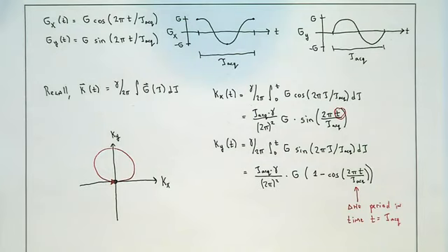So just in steps, essentially, we apply our RF pulse, and then our slice select gradient, and then the phase gradient, and then the frequency gradient. And that captures one row of k-space. And then we go back and do another one, and that captures another row of k-space. So between the different echoes that we're capturing, we're using the same frequency encoding gradient, but we're varying the phase encoding. You got it. And how are we varying the phase encoding? Is it the time or the amplitude?